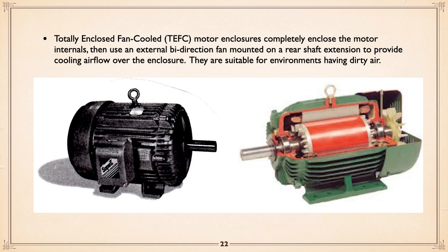Next comes TEFC, totally enclosed fan cooled. If you look at the cutaway, while the original fan is still there and spinning, moving air within, it's really just moving it a bit. The real cooling fan is at the end, the back end opposite the output shaft, in other words on the right with the green motor there. And the motor is enclosed completely. There's no air going in or out of the motor itself. The fan outside is blowing over the fins of the motor enclosure. They're suitable for environments having dirty air. You see them an awful lot in industry. That's pretty much the standard for industry.